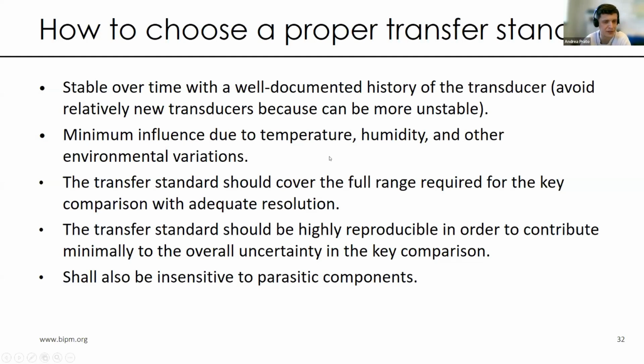And the transfer standard should cover the full range required for the key comparison with adequate resolution in order to minimize the influence of resolution. The transfer standard should also be highly reproducible in order to minimize the influence of repeatability and reproducibility in order to keep minimum overall uncertainty in the comparisons. And also it should be insensitive to parasitic components.